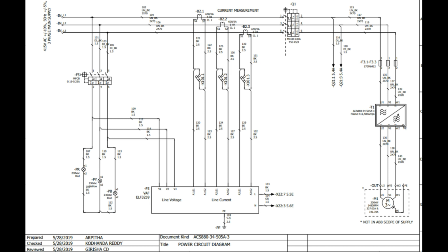So once we switch on this MPCB, we can see the indicating lamps glowing in red, yellow and blue color. With the same tapping it is given to the VAF, that is the voltage, ampere and frequency digital meter. So it's a line voltage, here you can see this system will get. And again going back to the top, here we can see the current measurement.